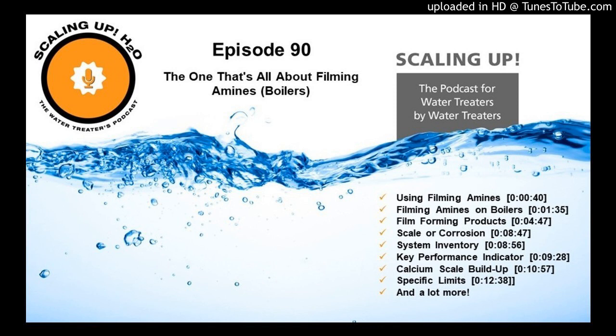So if you have a situation where you're heavily scaled, then maybe doing an acid cleaning ahead of time and just getting it out to begin with, right? Clean it off, clear it out to begin with, and then going in with your filmer to scrub the rest and film the system over and protect the metals. It's just going to accelerate your rate of success, right?